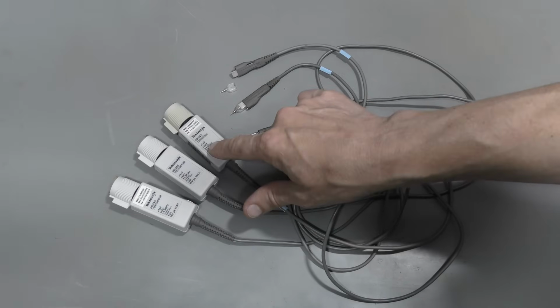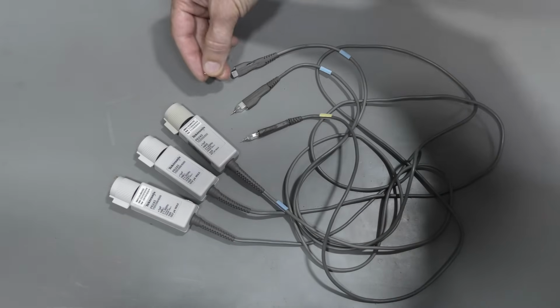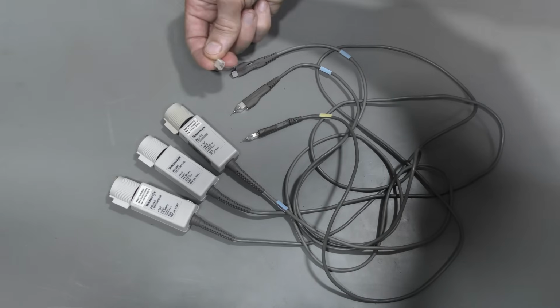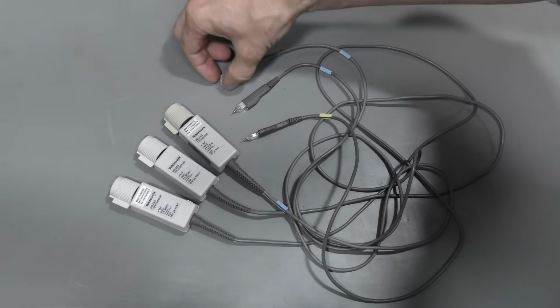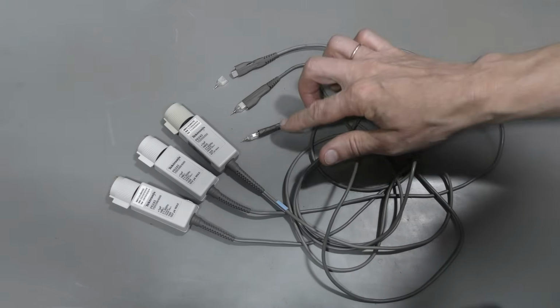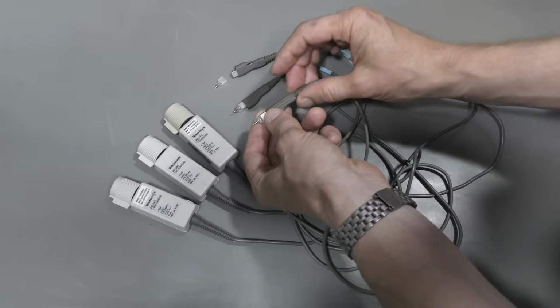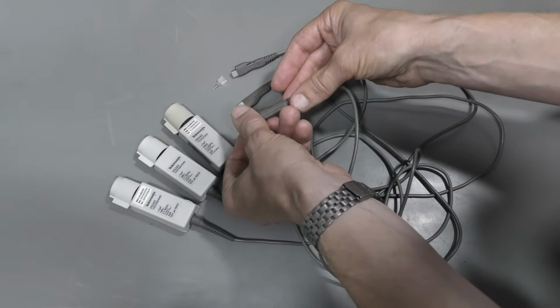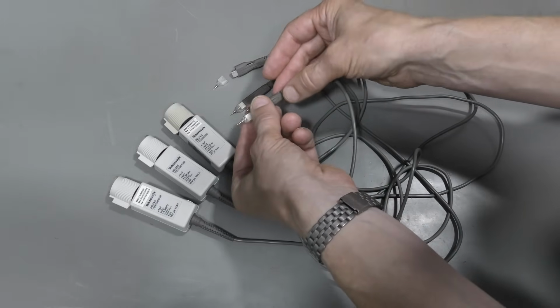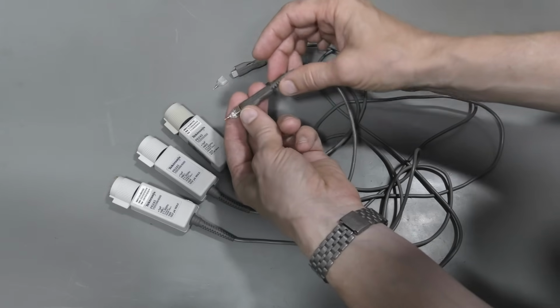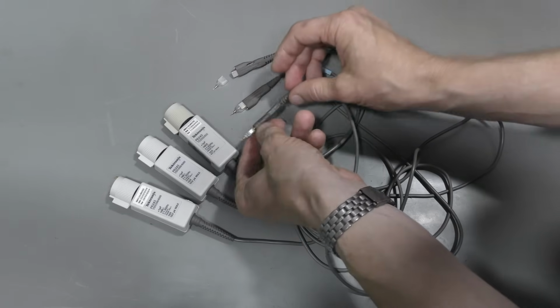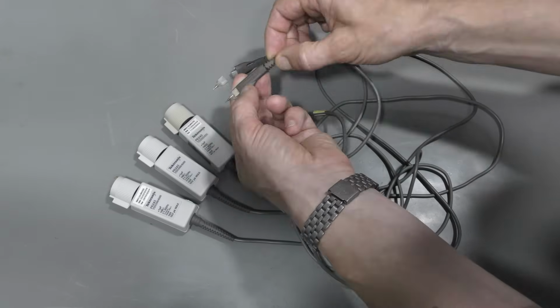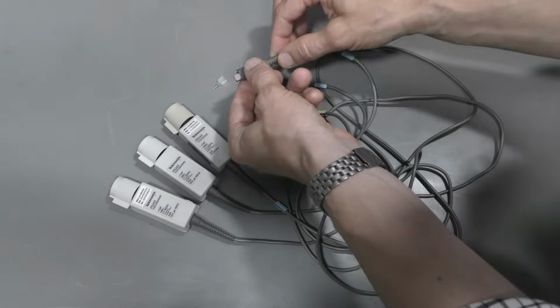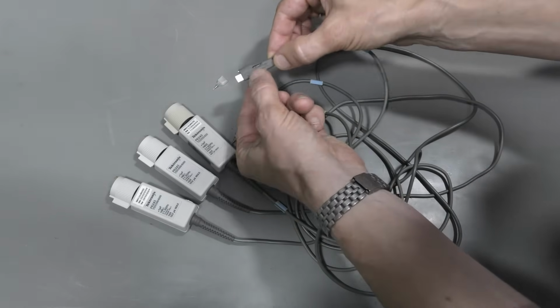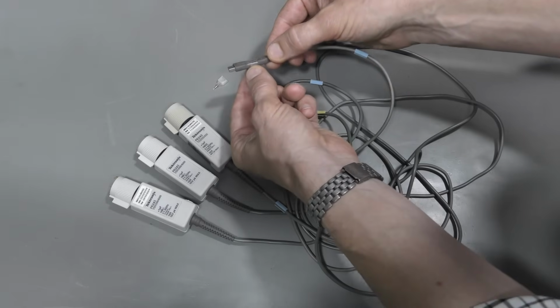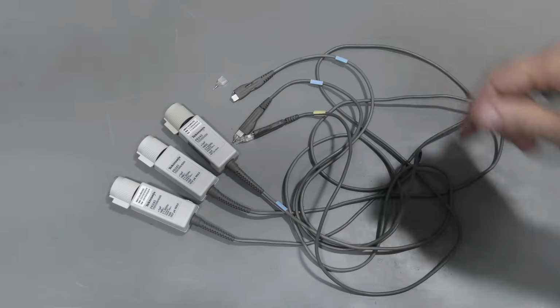And the third one has a problem with this tip cap. It was cracked and glued and now it is loose, falls off. And all 3 have problems with these rubber covers. They feel sticky, looks like the rubber is disintegrating. Strain relief here is completely broken, so is this one. This strain relief is still okay, but there are holes here and it also feels sticky. So let's see what we can do.